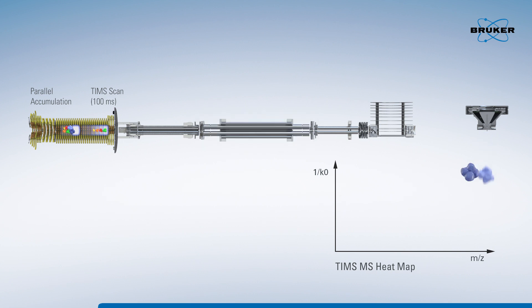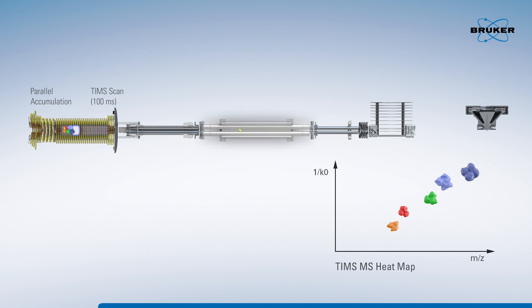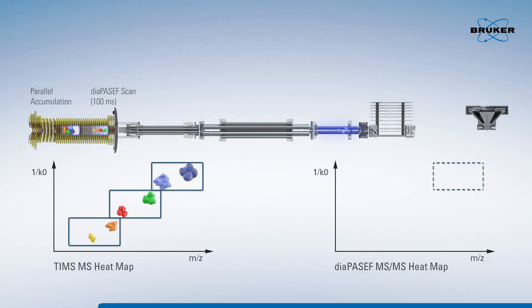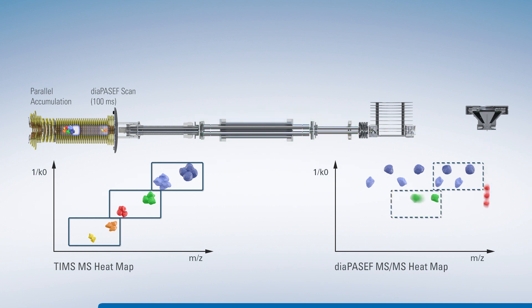Bruker and collaborators realized that a DIA approach using PASEF could take advantage of the correlation between ion mobility and mass. This technique, known as DIA-PASEF, uses windows that start at high mass as larger species elute at the beginning of the TIMS scan, sliding down to lower mass windows as the TIMS scan continues.